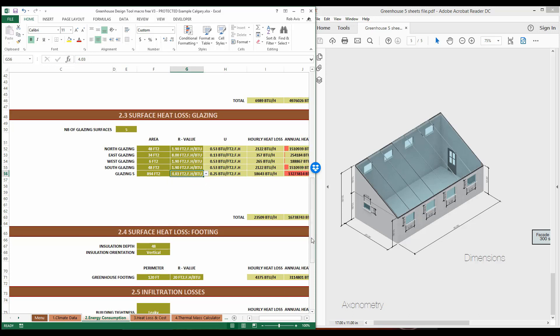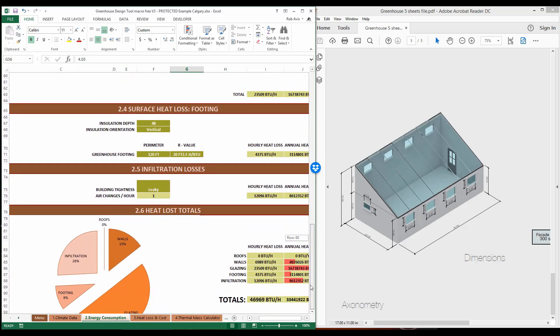So if we choose an R value of 4, take a look at what happens to your annual heat loss — it is greatly diminished. Your peak heat load is also cut down by about a factor of 33%. Play around with different R values in this model and see how low you can go with regards to your peak heat loss and annual fuel consumption in order to maintain the conditions inside this greenhouse that you set in the climate model. You're now done the energy model and can move on to heat loss and cost.